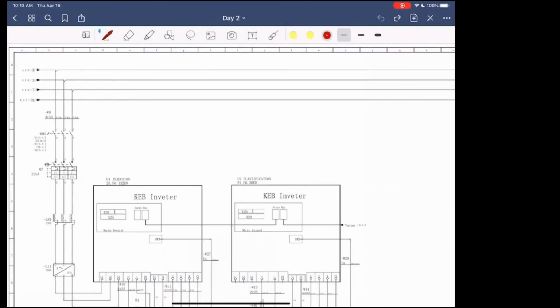Each line from there feeds through this KM1. KM1 is your contactor when you push your drive energize button. It goes through Q2, which is a 225 amp disconnect. It goes through your line filter and your reactor.